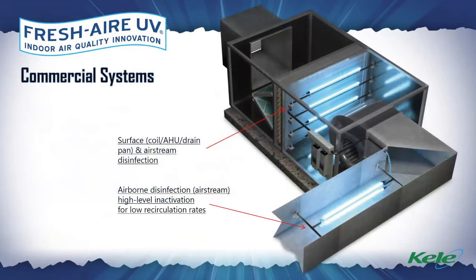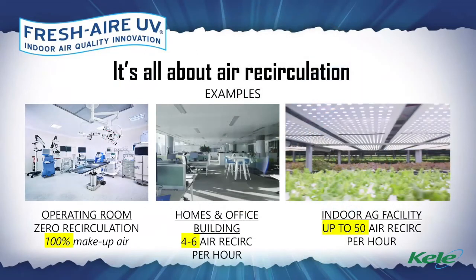So for offices, schools and shopping malls, I like to switch gears and go with the coil mount solution. And the reason why I like to go with that solution is because let's not lose sight that the coil and the drain pan is a source of biological contamination. And there is the additional benefit of improving equipment efficiency. And typically by putting enough UV systems, as you see here, on a coil, we will have enough dosage to effectively address the moving air as the air continually recirculates through the facility. So I do like to use the coil mount solutions because it really does address a lot of IAQ issues, whereas the duct mount unit really is specific to high level airborne viral or bacterial inactivation.